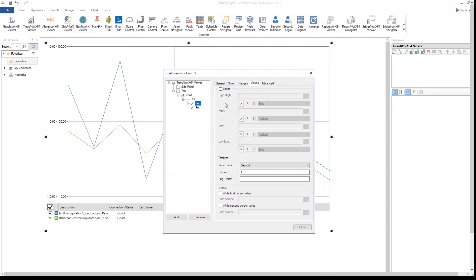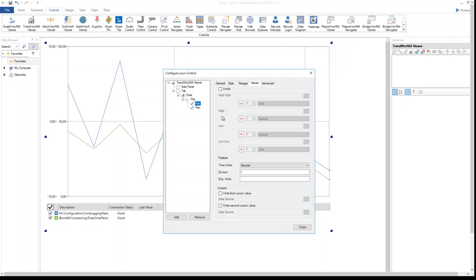As far as values, I can in runtime mode set and enable four different horizontal lines which will show me when the value visually, graphically, is underneath or is exceeding different thresholds. Be careful, this does not mean that I'm generating alarms right here, but I'm just setting graphically some lines that will help me understand when a signal is approaching some specific limit.